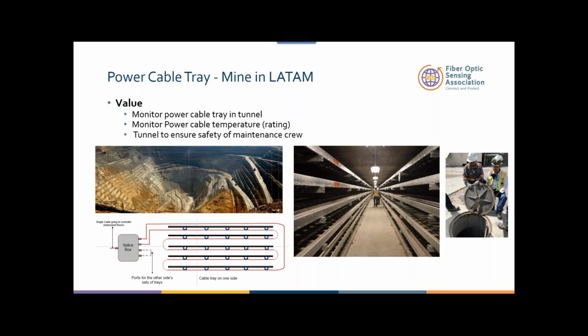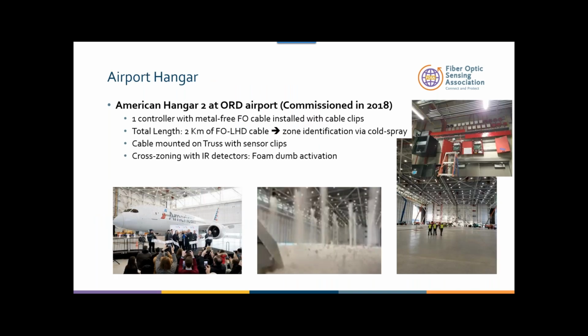Number one is the fire detection connection, fiber-optic linear detection. The second thing is to be able to monitor the temperature within the tunnel. In that tunnel, you can see the human beings walking in there. You can activate the fan to say the tunnel is too hot, the cables are overheating, send an alarm to activate the fans within the tunnel. The second thing is to be able to stop any human being going within that tunnel because it's too hot. It's very, very versatile in terms of what the system can do.